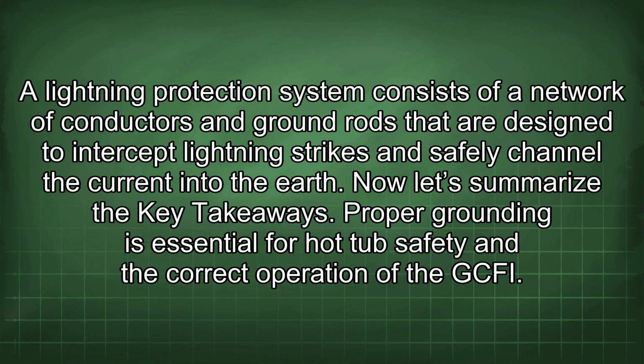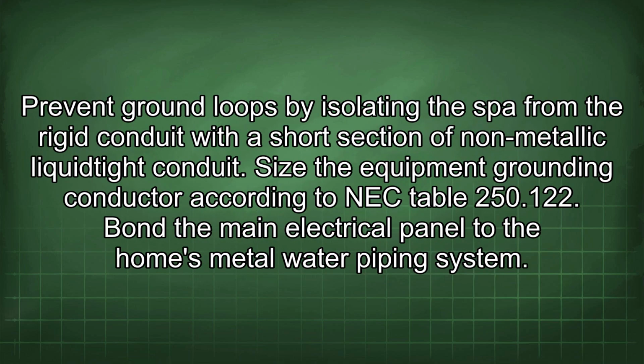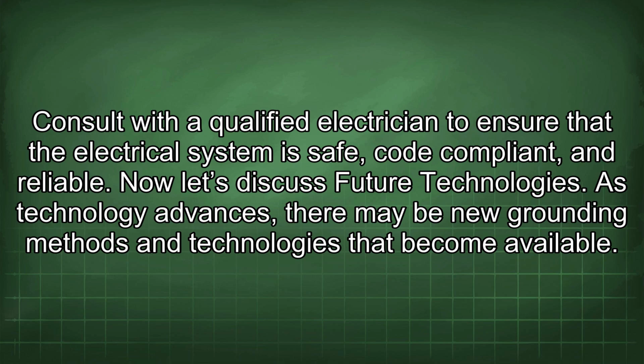Now let's summarize the key takeaways. Proper grounding is essential for hot tub safety and the correct operation of the GFCI. Prevent ground loops by isolating the spa from the rigid conduit with a short section of non-metallic liquid-tight conduit. Size the equipment grounding conductor according to NEC Table 250.122. Bond the main electrical panel to the home's metal water piping system. Consult with a qualified electrician to ensure that the electrical system is safe, code compliant, and reliable.